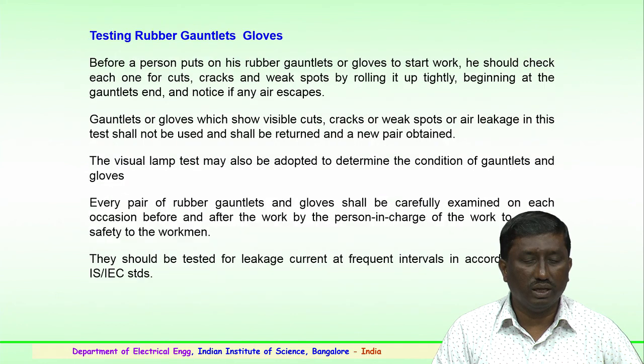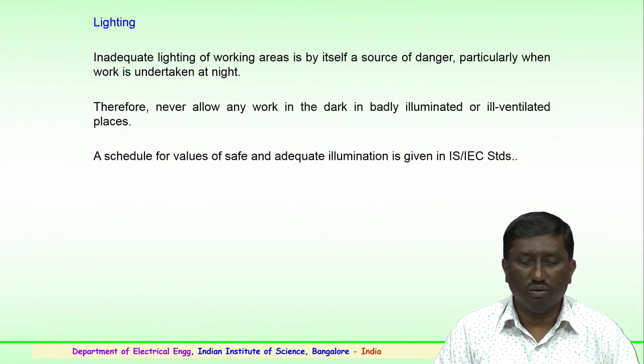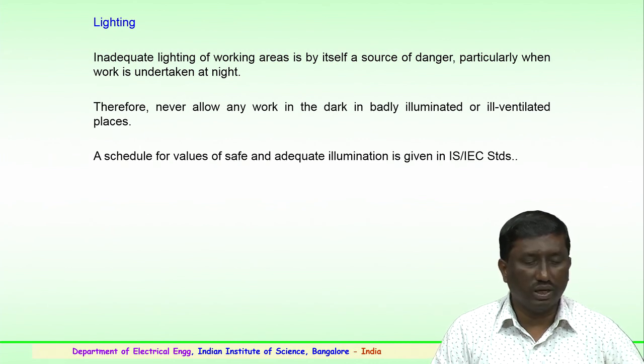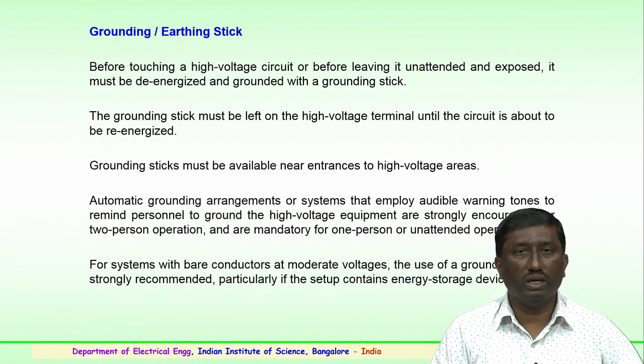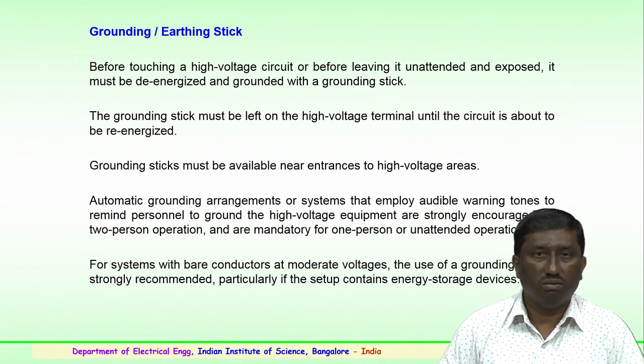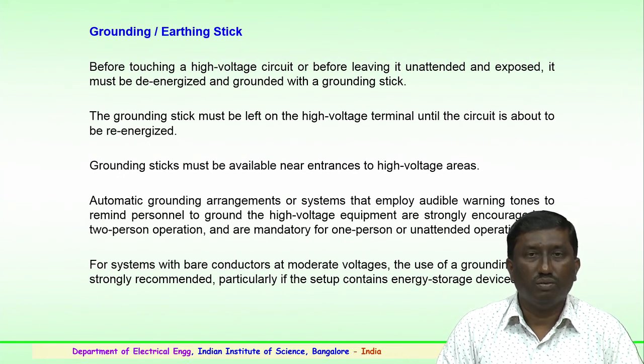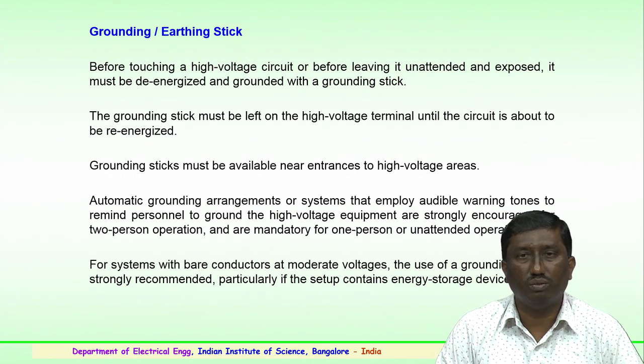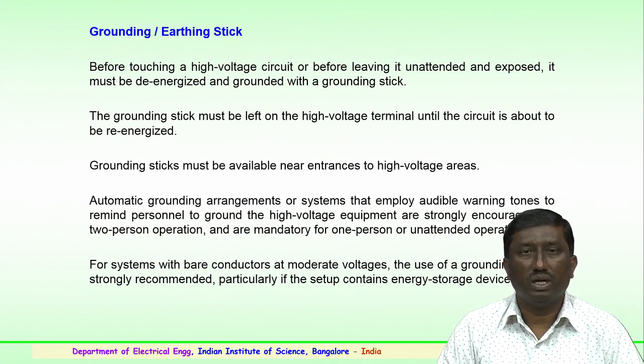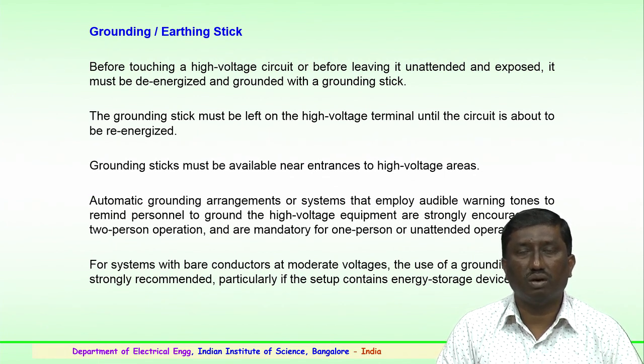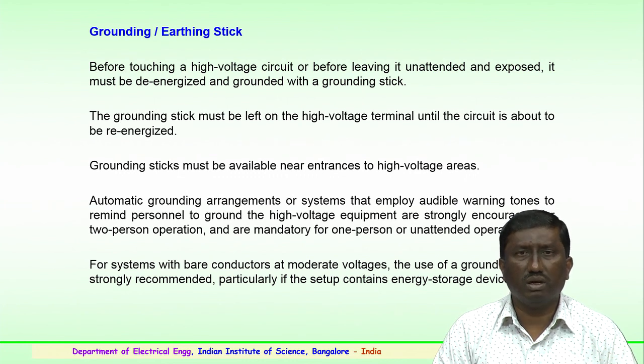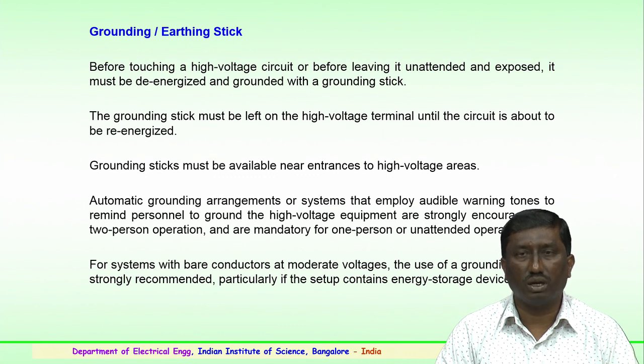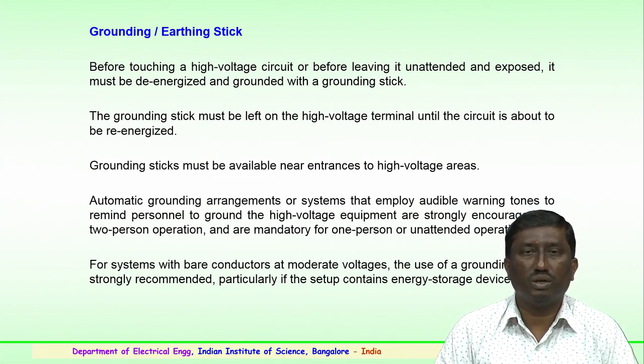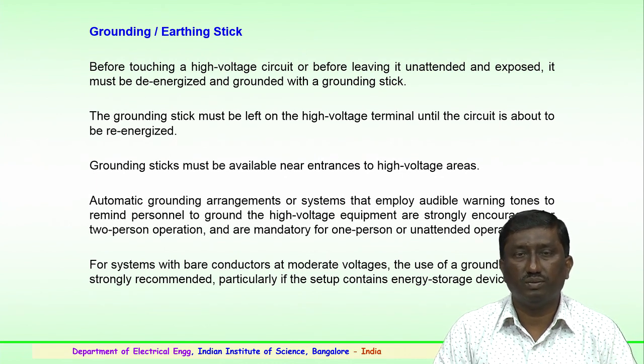So, lighting, as mentioned earlier, is very important. So, proper lighting has to be done. So, finally, there is the grounding or earthing stick, which is a very important device. Before touching a high voltage circuit or before leaving it unattended and exposed, it must be de-energized and grounded with a grounding stick or earthing stick. This grounding stick must be left on the high voltage terminal, permanently connected, until the circuit is about to be re-energized in case of maintenance.